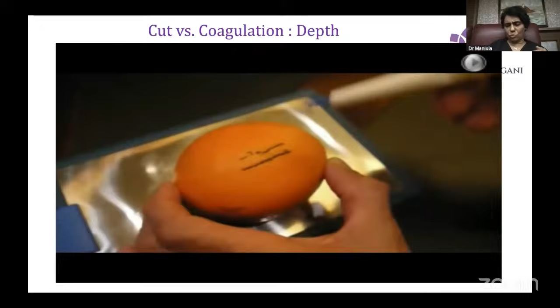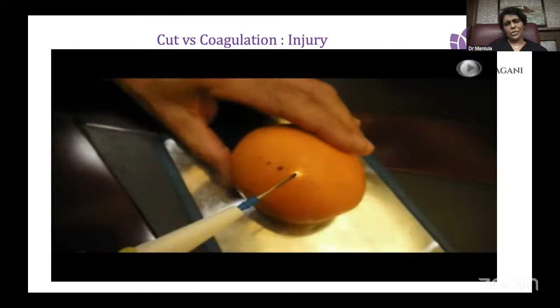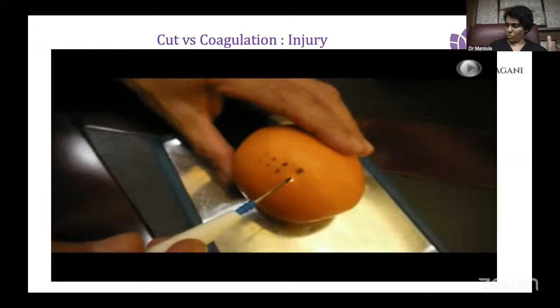If you take the same thing as an injury, first we are using coag. You can see the finger going to coag. So 1001, 1001, 1002, 1001, 1003, 2, 3, and 4. Then again, 1001, 1002, 1003, 1004, 1005, 1006. Then you see the lateral thermal damage with coag, and now you see the cutting current, 1001, 1002. The lateral thermal damage is less. So if you are continuously using a cutting current, lateral thermal damage is less. If you are using a coag current, lateral thermal damage is more. This is the point you need to understand.